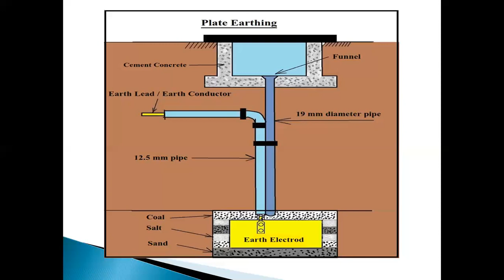The water is poured for increasing dampness and moisture, which in turn reduces the earth resistance. At the top, a cement concrete work is made to protect the plate from mechanical damage. The concrete work is provided with a cast iron cover for periodical opening and also inspection. The cover is made in such a way that whenever there is a need for maintenance or checking, it can be easily opened. With this, our plate earthing has been completed.